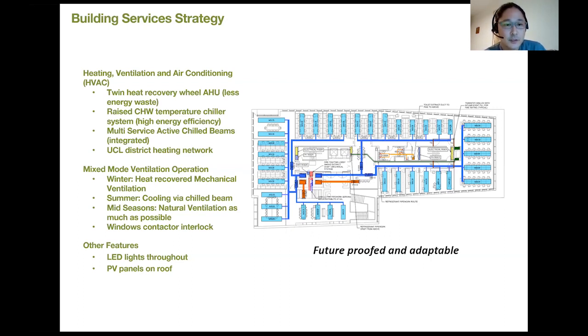This system uses raised chilled water temperature. Rather than 6-degree conventional fan units, they use up to 14-degree temperatures, achieving higher energy efficiency in the chiller system. Together with architectural coordination, this has been selected to incorporate lighting, fire alarms, and other sensors.